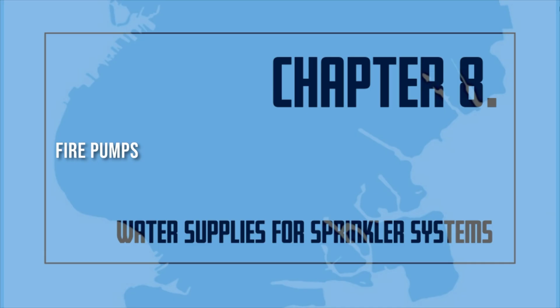Fire pumps shall be sized to satisfy the hydraulic requirements of the sprinkler system. A fire pump having both a reliable source of power and a reliable suction water supply is an effective piece of equipment. A suction water supply is simply a body of water that the pump can draw water from. Fire pumps are commonly used because they can pump water into the sprinkler system under high pressure. With a good water supply, a fire pump can pump water into a sprinkler system for a long time.